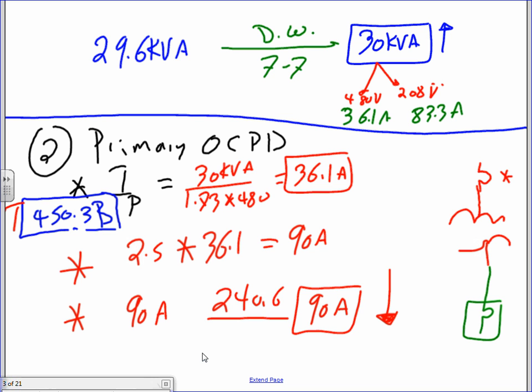So here's the size of my fuse. Then, Adam, when you build the Revit schedule, you're going to put this 90 amp circuit breaker. How is this related to the Revit, guys? We're going to size one for Revit right now. You're going to go to Revit, pick a 90 amp fuse, and change the schedules to 90 on the primary side. Any comments, any questions? Karen, does it make sense? Okay, so we size the fuse or the circuit breaker on the primary.